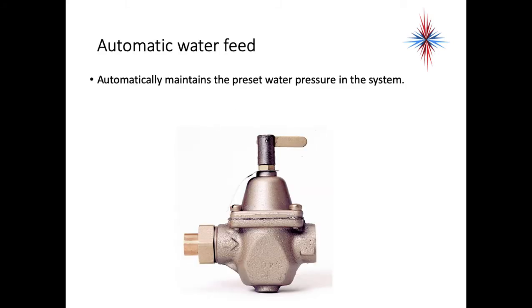Automatic water feeds are required in all hydronic systems. They maintain a preset water pressure — if the pressure drops too low, the feed opens slightly to allow new water to enter the system. Along with the low-water cutoff, this ensures water always remains in the system.